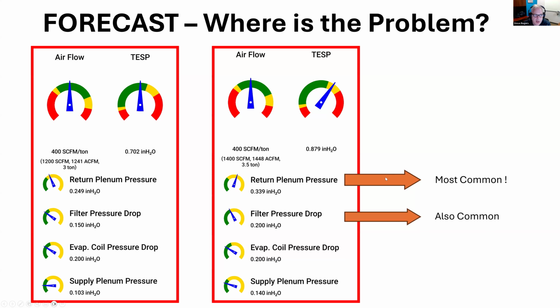Also quite common is filters that are not large enough or not deep enough. So if I've got a 16 by 20 filter on a 4-ton system, a 16 by 20 by 1, for example, on a 4-ton system, that's not big enough. It will always cause a major restriction on a 4-ton system. And deeper is better. Normally, if you go from a 1-inch deep filter to a 4-inch deep filter, approximately you'll cut the pressure loss in half. And if it's apples to apples, if I've got the same brand and the same MERV rating in a 1-inch or a 4-inch deep filter, usually the 4-inch deep will have something like half the pressure loss.